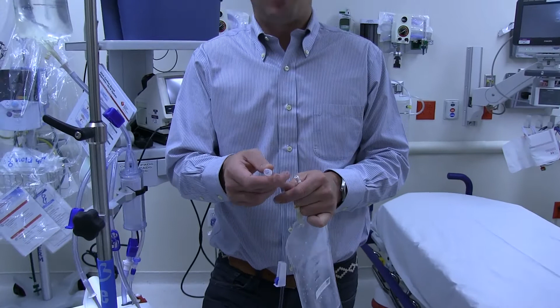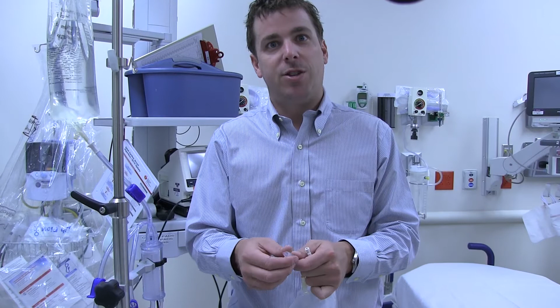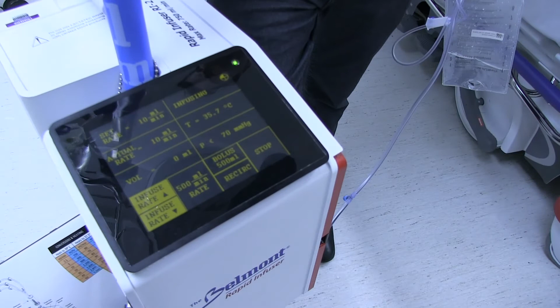You get the best flow if you strip the catheter right down to the hub and make the connection there, because if you're going into an 18 gauge with a loop and a stopcock, it's going to jam it up and cause pressure when you're trying to go fast. So make your connection right to the hub of the catheter. When you're ready to go, press infuse, and it starts you out at 10 a minute. The heat's on, you can start hanging your blood products now.